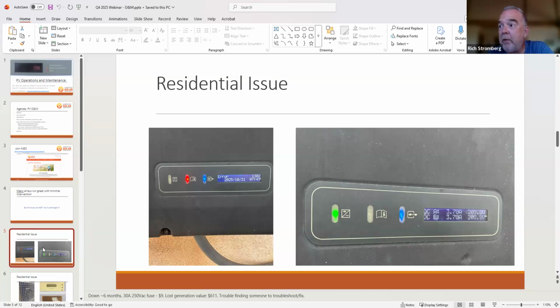So anyway, he sent me this photo on the left, and it says error 1302. That morning I pulled that up and it said, oh, AC grid connect issues. This might be easy. Sure enough, what we found is one of the AC fuses between the inverter output and, on the outside, there was a disconnect, an AC disconnect going to his service panel.